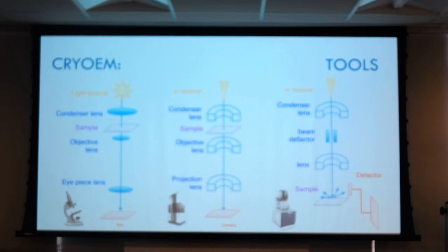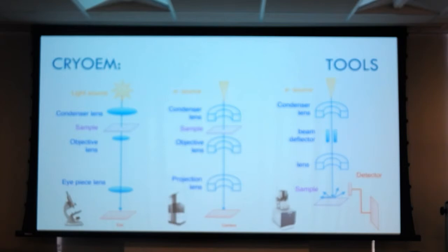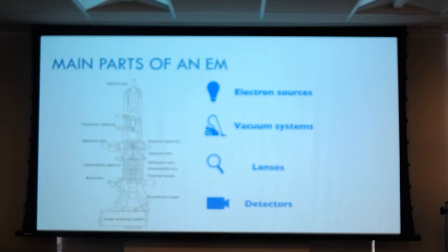Does anyone know the typical magnifications for an electron microscope? In papers you've been hearing about two to three angstrom resolution reconstructions. So if you're at two to three angstroms, what's your minimum pixel size? Around 0.8 to 1 angstrom. Now what's the magnification — a pixel for a detector is on the order of 5 to 14 microns, so you're on the order of tens of thousands like 30,000, 40,000, 50,000x. That's also another consideration when you make a microscope — can you reach a magnification that gives you a resolution of interest? That segues into the four parts of an EM.